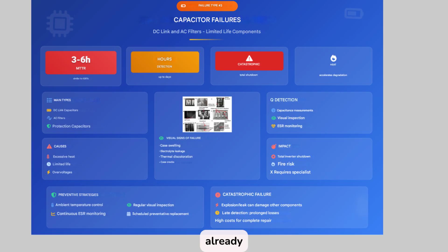The most common failures are usually caused by excessive heat, overvoltages, or simply the natural aging of the component. Visible signs of degradation, such as casing swelling, electrolyte leaks, or thermal discoloration, help us identify the problem, but often these signs appear when the component is practically at its operating limit. Therefore, it is essential to monitor parameters such as capacitance and ESR to detect patterns of deterioration before complete failure occurs. When this happens, the inverter stops, and we need qualified technical personnel to perform a repair, which is not always simple.